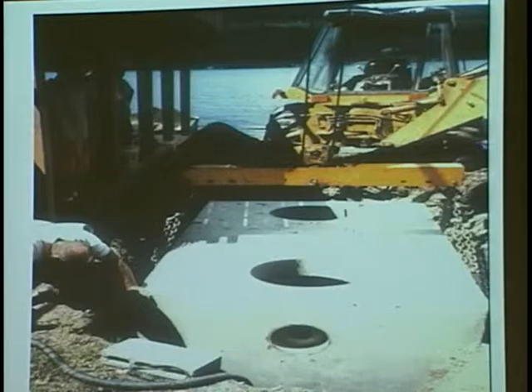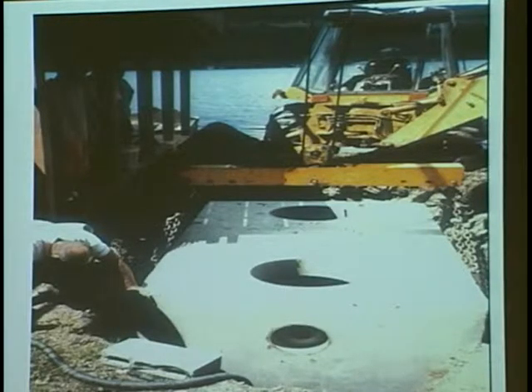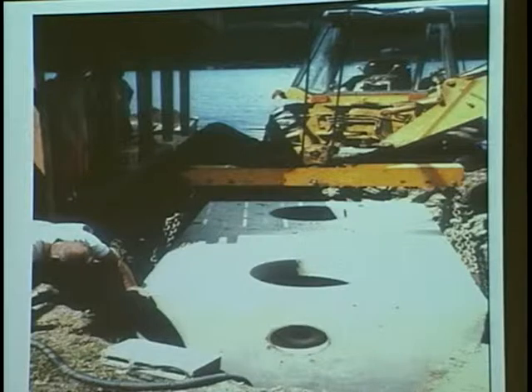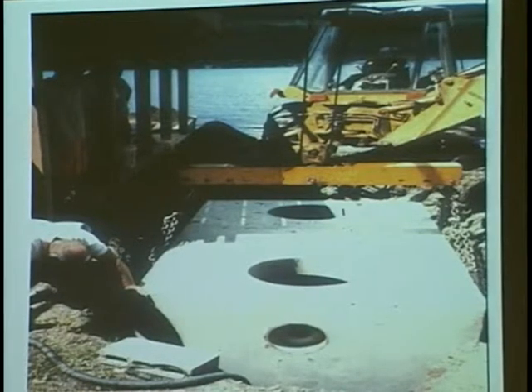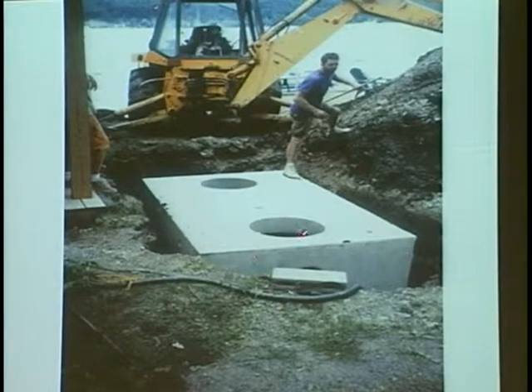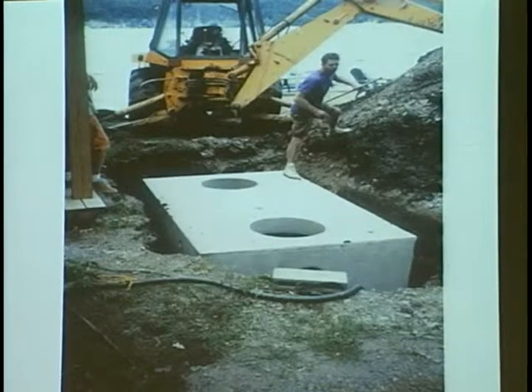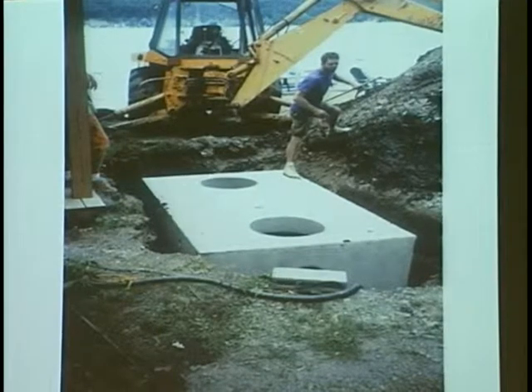The homeowner is required to have a high-level alarm on it with the alarm set with one day's capacity left before they need the pumper, and they are to send me a copy of their pump-out receipts — one method of trying to keep track to make sure they are being pumped out when needed. There's that coarse fractured shale — that's what all there is out there around that lake. Look how thick this slab is — it's a live load slab on this tank. Why? That's their parking spot. That's how small these lots are. We can't do anything else.